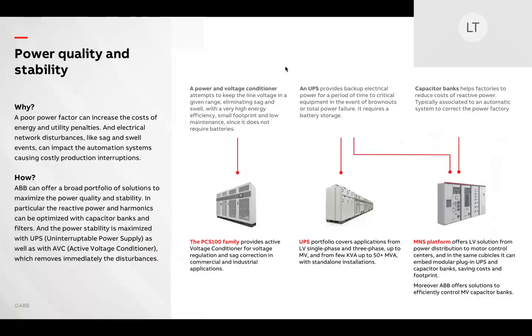A low power factor might only be one of the symptoms of a range of power quality problems that can reduce both the reliability and the efficiency of your electrical equipment on your network. A full ABB survey will detect any power quality issues such as harmonics, flicker, and unbalanced loads. We can then draw on our range of state-of-the-art equipment, including active filters, to provide you with the ideal cost-effective solution. And last but not least, we have power and voltage conditioners.